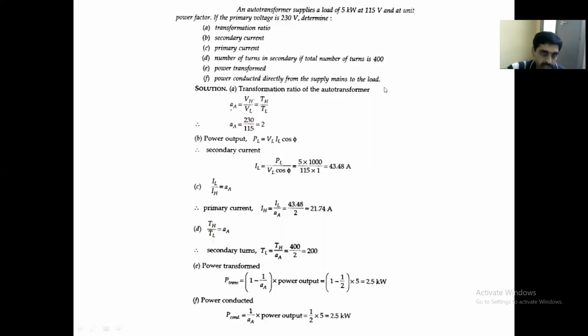So these are various questions. So first step is you calculate A, the transformation ratio, which is equal to VH by VL or V2 by V1. You can take anywhere. There are different nomenclatures. That is N2 by N1 or TH by TL. 230 by 115, 2. So what is the power output normally? P is equal to VI cos phi. Therefrom you can calculate the secondary current. P by V into cos phi. So this is the secondary current, 43.48 amperes.